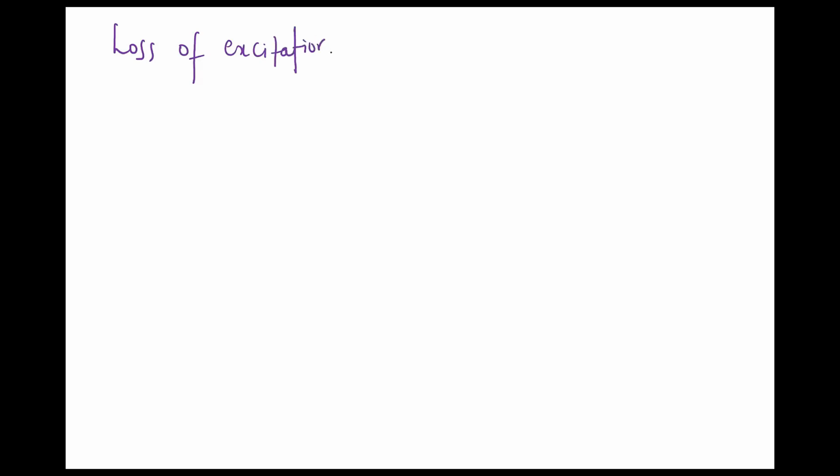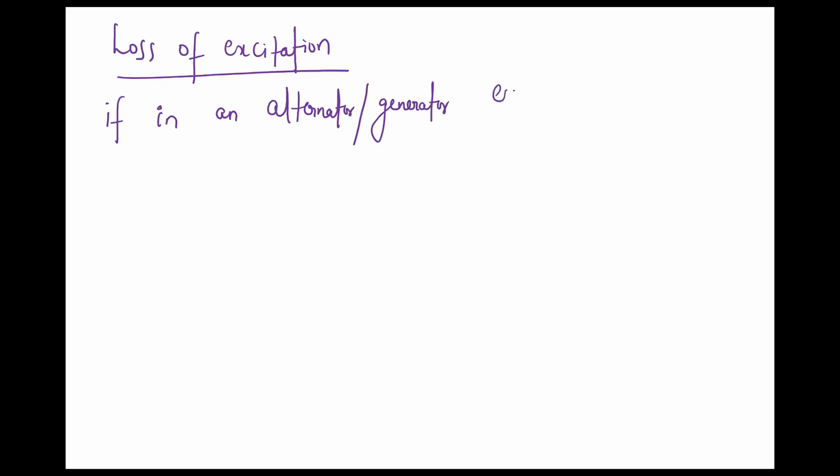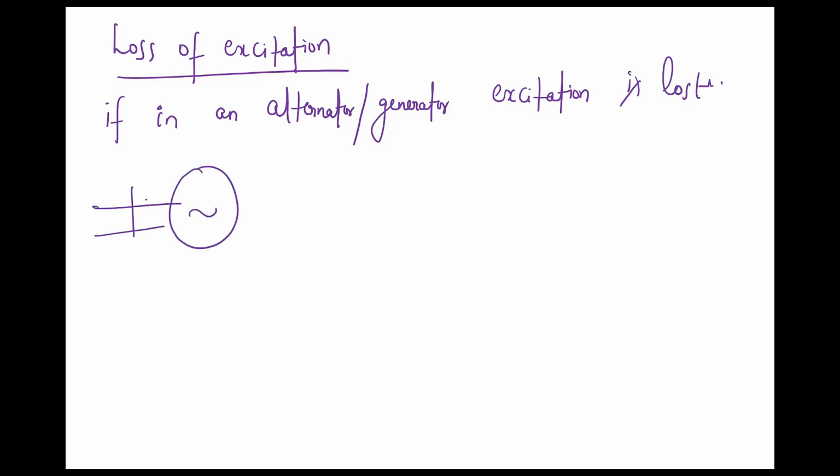So if in an alternator or generator, excitation is lost, okay, this is the bus bar, it will supply real power to the bus bar, but it will draw huge amount of reactive power.